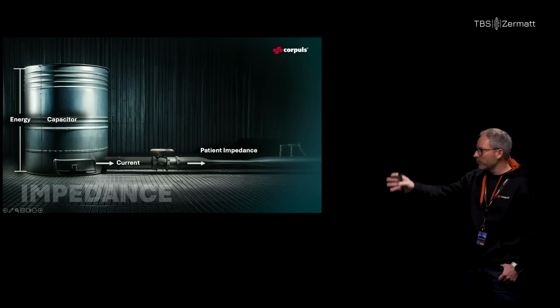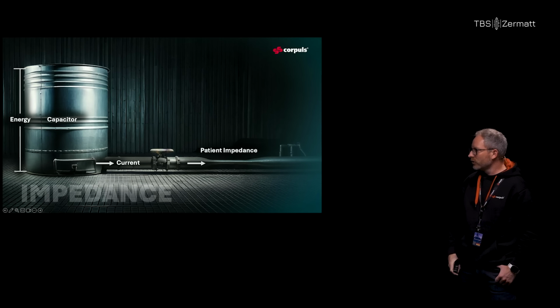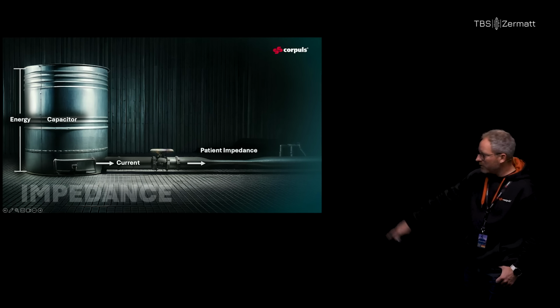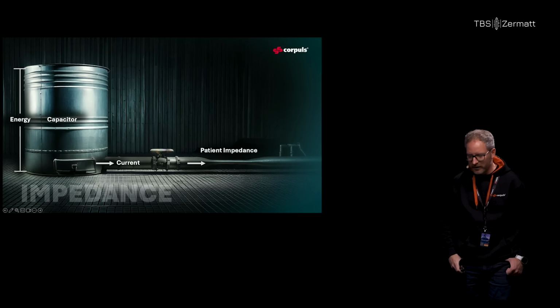Like you see here on the left-hand side, that barrel labeled capacitor, kind of like compared to a water tank. This is where our charge goes into, and once it's full we want a controlled release of the current, like we see here in the pipe, and then in the middle where it says patient impedance, the pipe all of a sudden gets smaller.